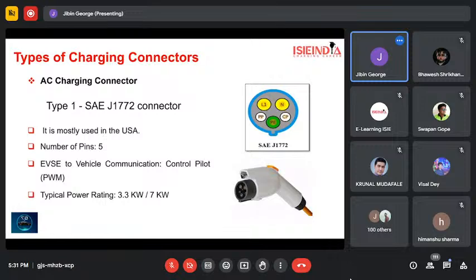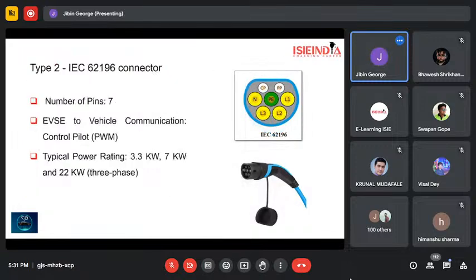Next is type 2. In type 1, it is single phase; in type 2, it is 3 phase. Its standard is IEC 62196. In this connector, there are a total of 7 pins, and it also comes with a communication network. This pin is also called the control pilot. The power rating is from 3.3 kilowatt to 22 kilowatt. Since it is 3 phase, it has a higher power rating than type 1.